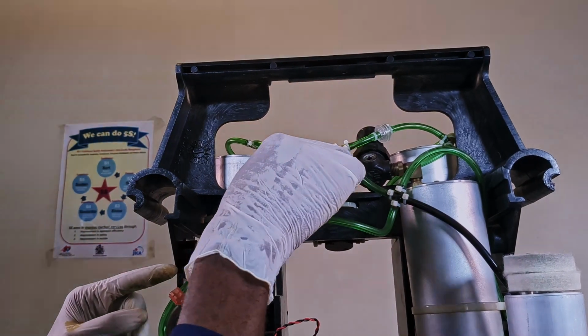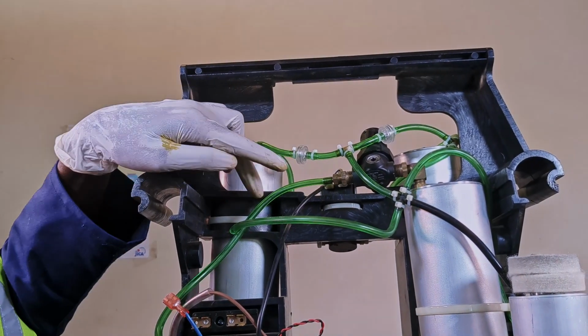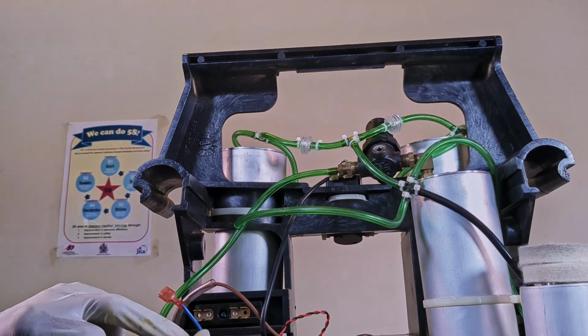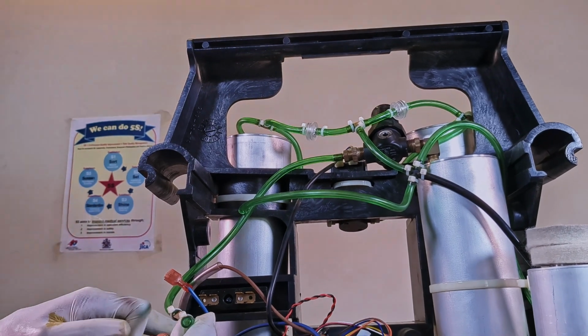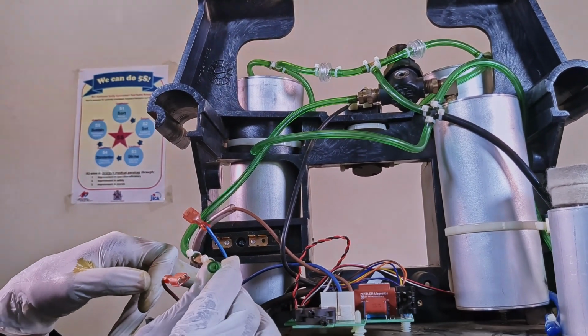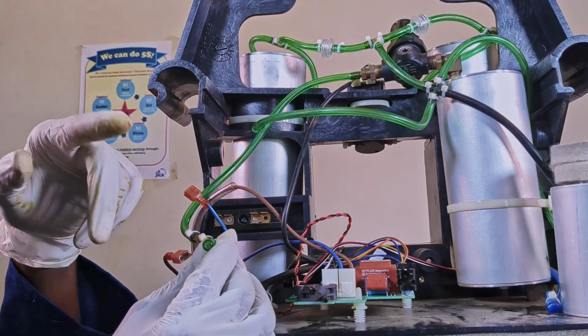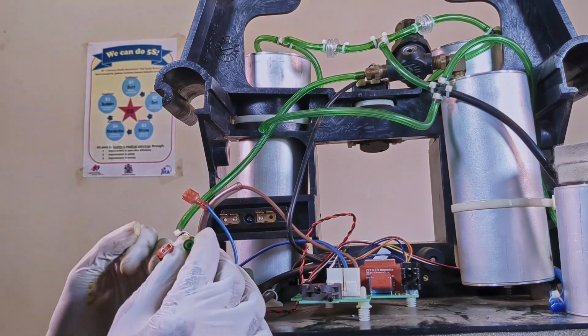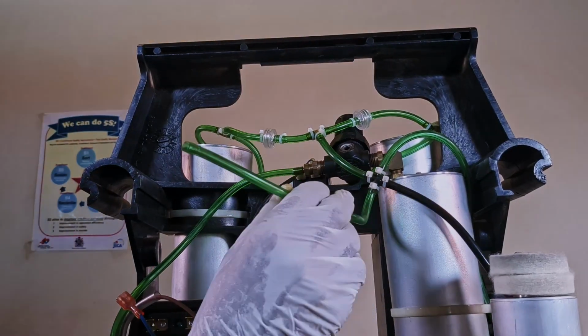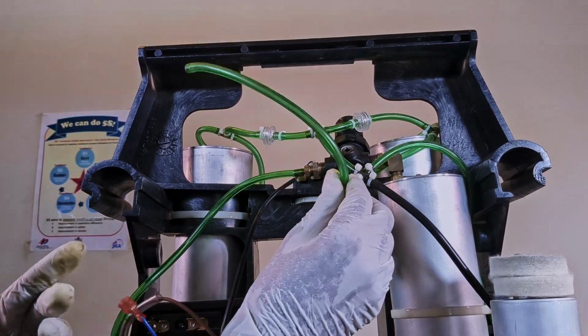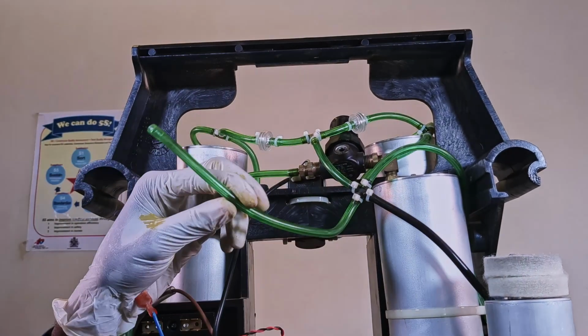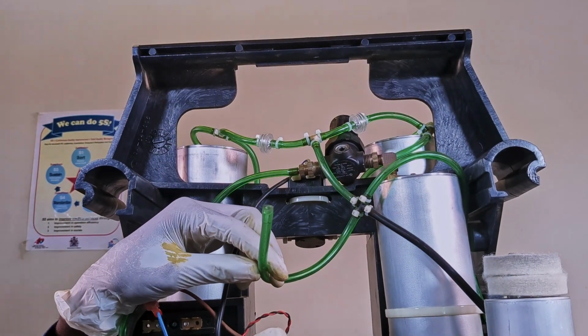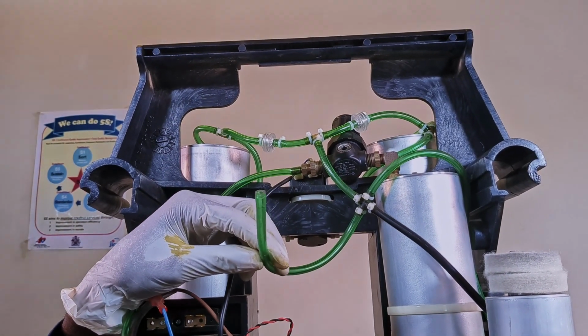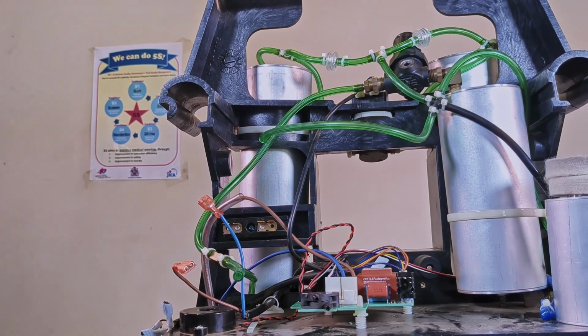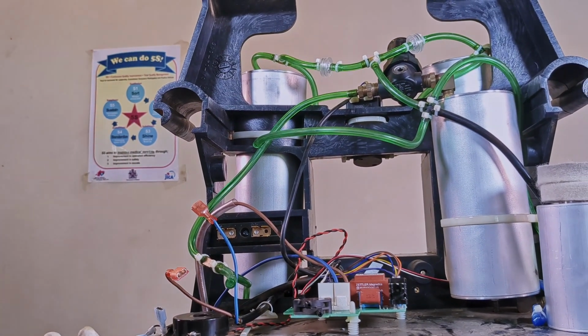And from the pressure regulator, oxygen goes to the inlet of the flow meter and then to the oxygen monitor, from where it is connected to the oxygen outlet port. And over here, we also have another tube that is connected to the pressure transducer, which is on the main control board. And that concludes the pneumatic system of this oxygen concentrator.